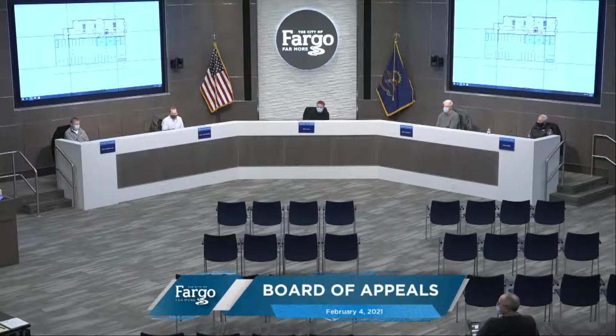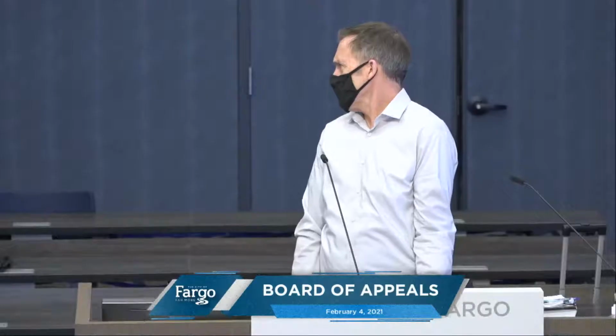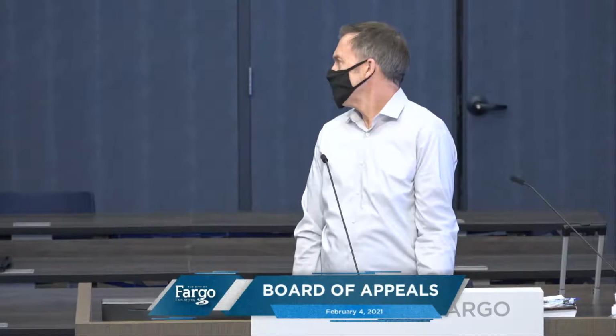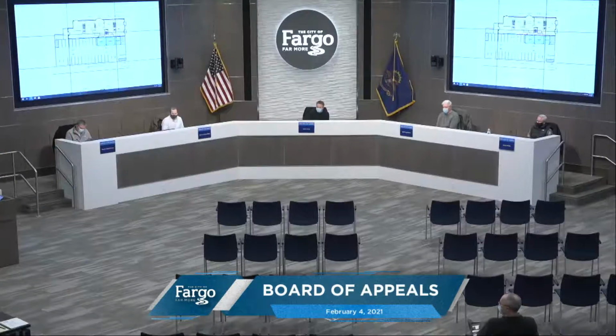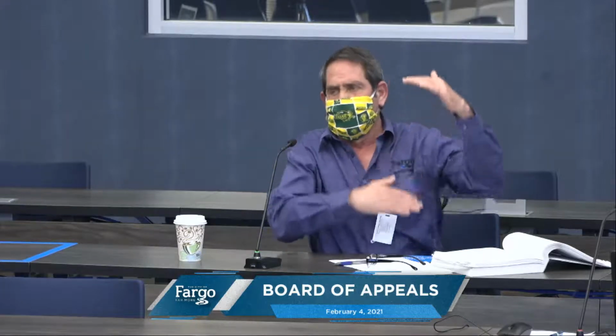Sure, you remember the construction type? I believe it's 2A. Well, I've been kind of silent here. I'm the reviewer. And there's one issue that Tom isn't bringing up. If you're separated horizontally by the deck, but I can drive from tier to tier to tier, how are you separated? There is no separation. I can't get there.